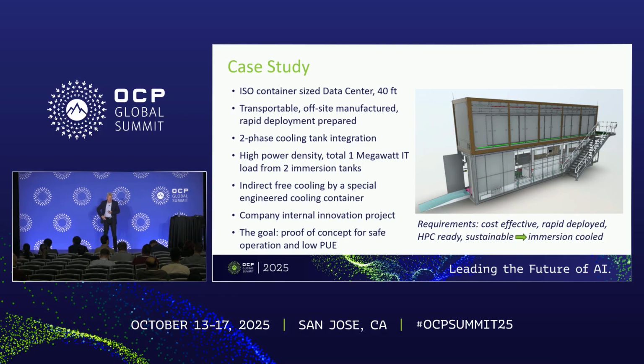Two-phase tanks are in, and we were deciding for high performance computing, so it should be HPC ready - we decided for a megawatt. Cooling generation is always important, so indirect free cooling with no chillers was the decision here. We made it company internal, wanting a proof of concept and to measure the values. First, safe operation was a focus so people can work with it, then have low PUE and be sustainable. So requirements are cost-effective, rapid, HPC ready, and sustainable.